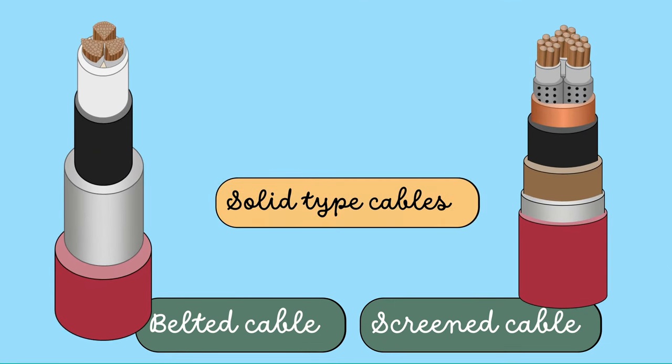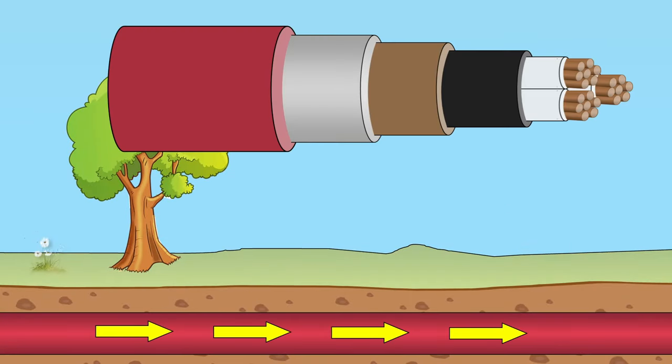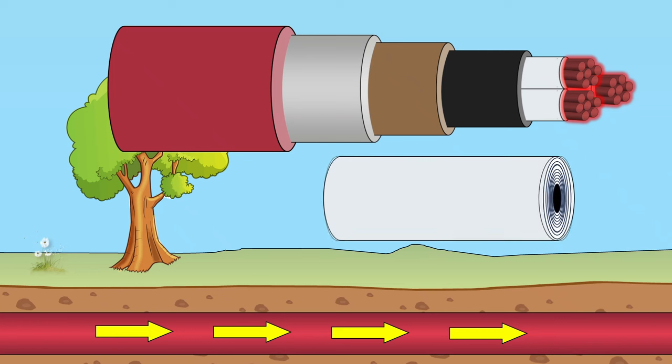These are called solid type cables because solid insulation is used. There is a problem with this solid insulation. When the cable carries the load, its conductor temperature increases. This leads to the expansion of paper insulation. This action stretches the lead sheath which may be damaged.